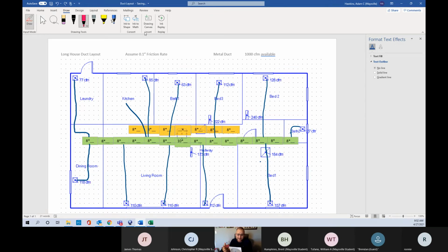He's a pretty slick guy. He worked with a contractor and they designed this themselves. So he's got this humongous flex, run all these feet to just take up space so that he delivers the right amount of air, but it delivers it really, really slow and really, really quiet. I never thought about it, but I always thought you're tied to this thing and you say, well, in order to move 100 CFM, I have to have 6-inch duct.